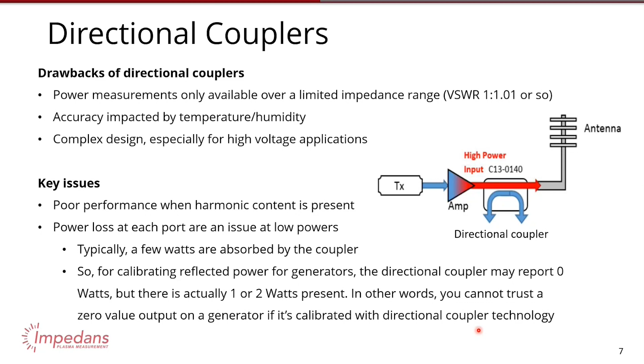So in other words, never trust a 0 output on your generator, whether it's on output power or reflected power. Never trust a 0, okay? If it's being calibrated with directional coupler technology, there is still likely power there. This is something we see surprisingly often.